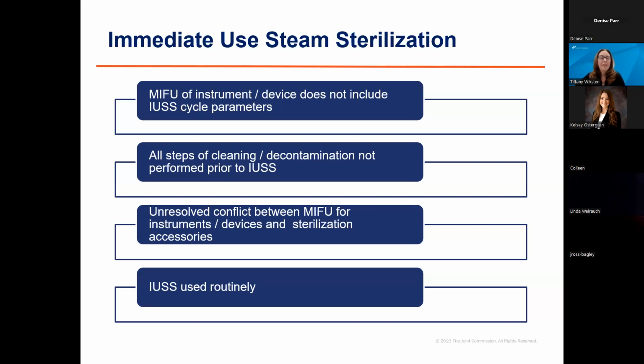Oftentimes the manufacturers of full instrument sets will say a full instrument set should not undergo IUSS, right? Because the process itself is inherently more risky. You have staff whose job is not dedicated to only performing cleaning, decontamination, inspection, and sterilization of the instruments. They're often doing several other things, but manufacturers' instructions for use often don't allow for immediate use steam sterilization of full sets. Another reason why we see immediate use steam sterilization that is really not an appropriate reason is if your vendors are not dropping their trays off in time, right? So you should have a contract with your vendors that says the trays are to be dropped off within X amount of time so they can go through terminal sterilization.